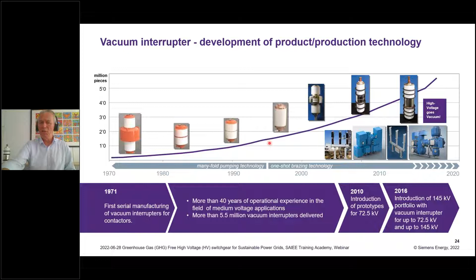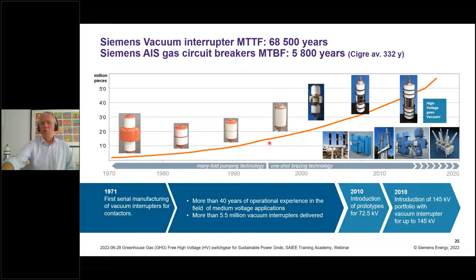On the right hand side, you see the 145 kV vacuum interrupter, which goes into the live tank technology and into the GIS technology. So this is the way forward - there are more than 5 million vacuum interrupters produced. We produce them on the same production line, with the same production technology as medium voltage, so we have very high reliability. Looking at reliability, I just want to give you a few numbers.